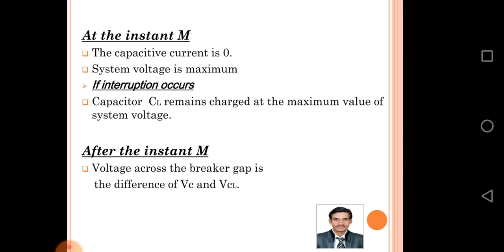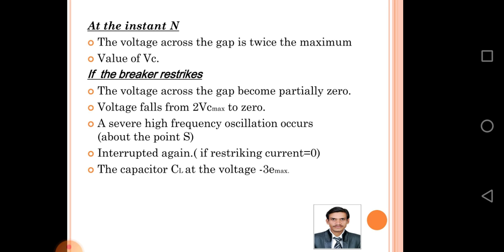After instant M, the voltage across the breaker gap is the difference of Vc and Vcl as seen in the figure. At instant N, the voltage across the gap is twice the maximum value of Vc. If the breaker restrikes, the voltage across the gap becomes partially zero — voltage falls from 2 Vc max to zero — and a severe high frequency oscillation occurs.